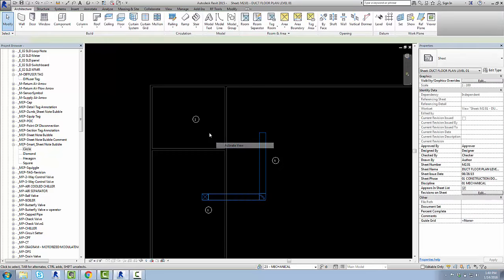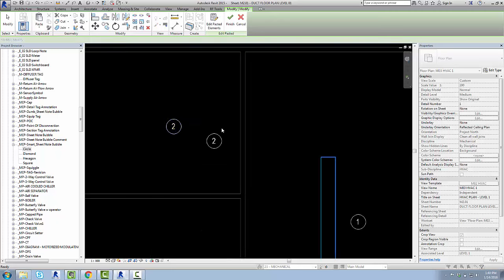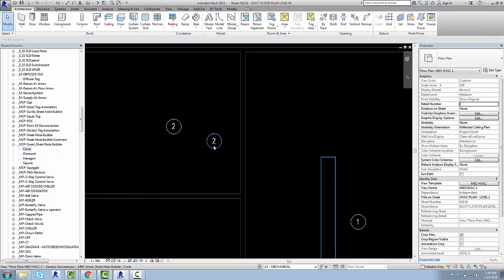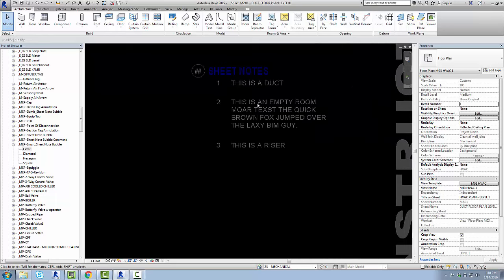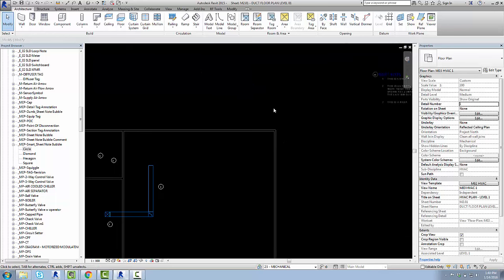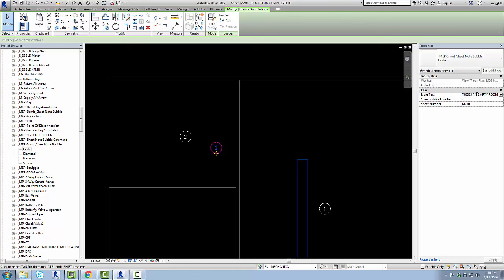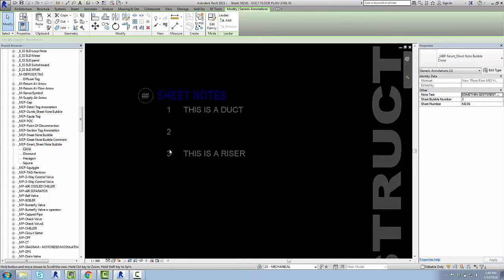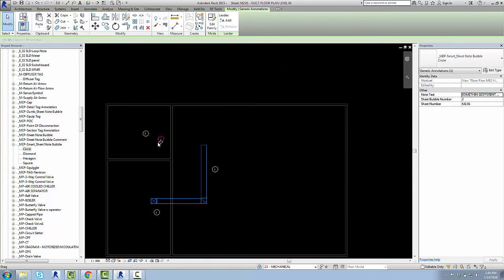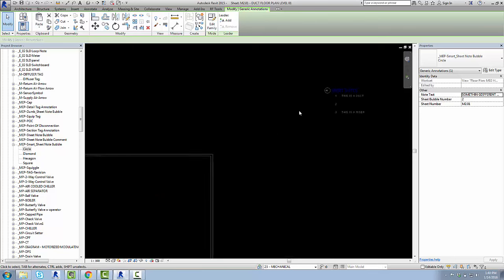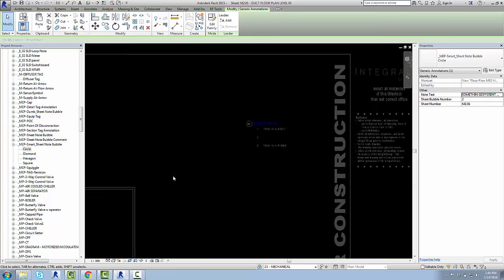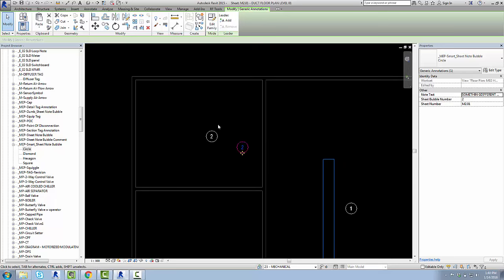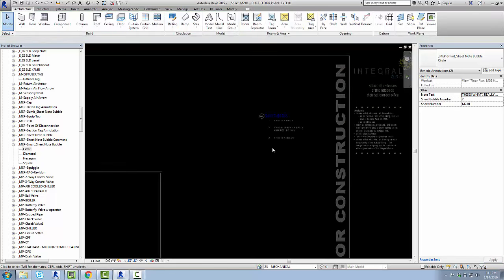And now, just also proving that even if you have multiple sheet notes of the same number, so I've got two twos in here. This is set not to itemize every instance, so I'm just going to have one row for that. Now, here's the thing, if I change this text to be something else, like something different, now this row is going to be blank, because that's an indication that I've told this number two to say one thing, and this number two to say another thing. Okay, and Revit goes, uh, what, blank, so you just got to make sure that they are consistent. And you can just multi-select and say, this is what I really want to say. And now they're both happy.